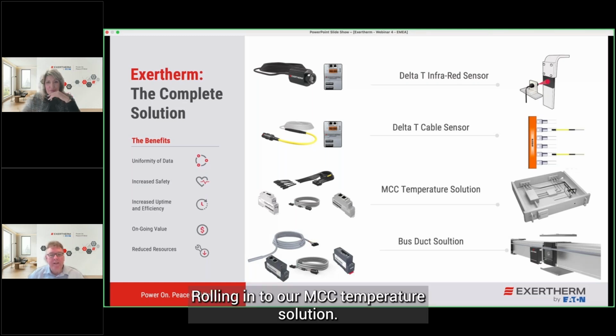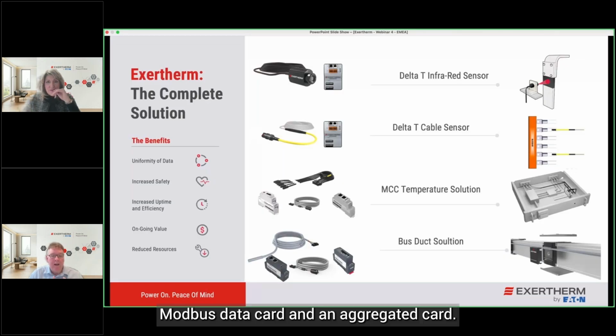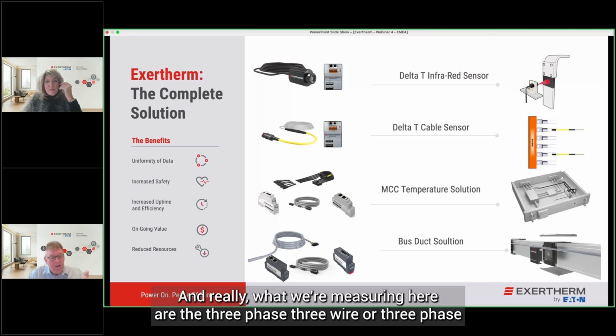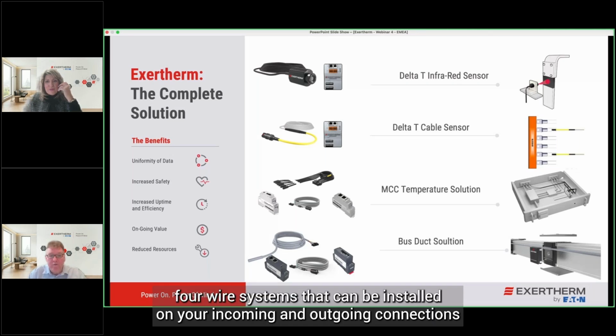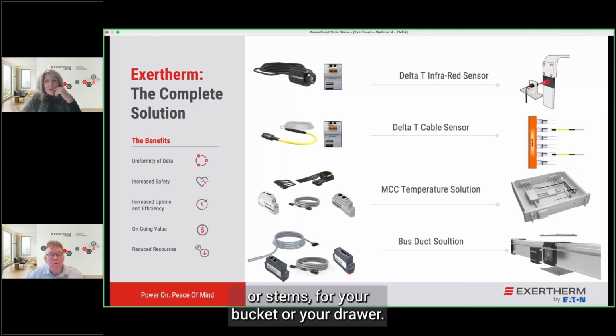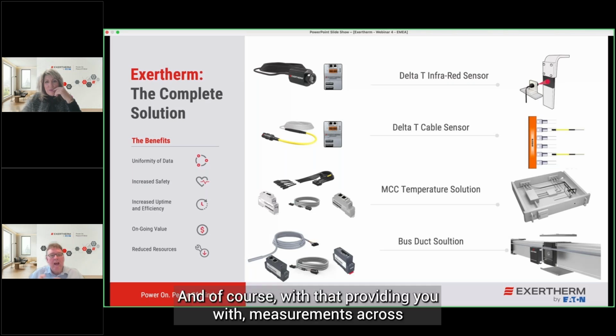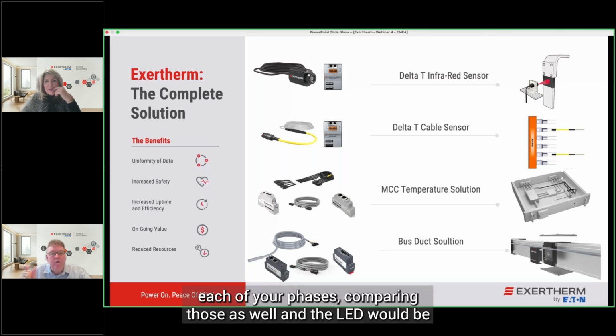Rolling into our MCC temperature solution, this comes standard with a loom, with an LED, a Modbus data card, and an aggregator card. What we're measuring here are either 3-phase 3-wire or 3-phase 4-wire systems, which can be installed on your incoming and outgoing connections, or stabs for your bucket or your drawer. And of course, with that, providing you with measurements across each of your phases, comparing those as well.